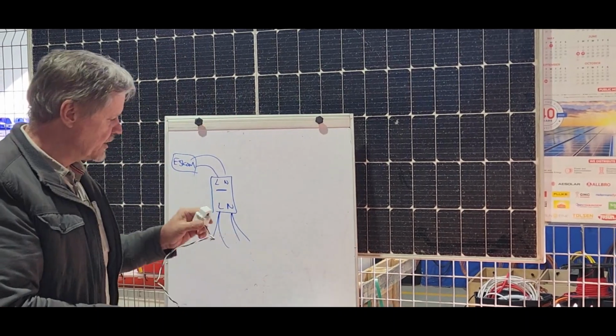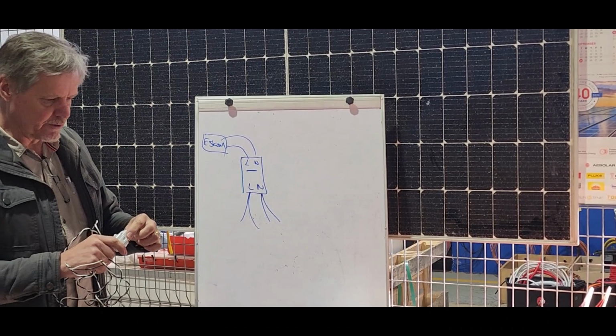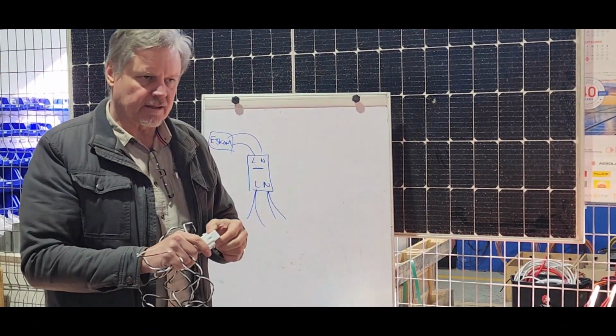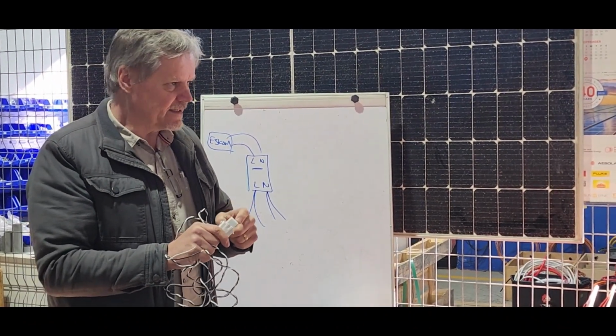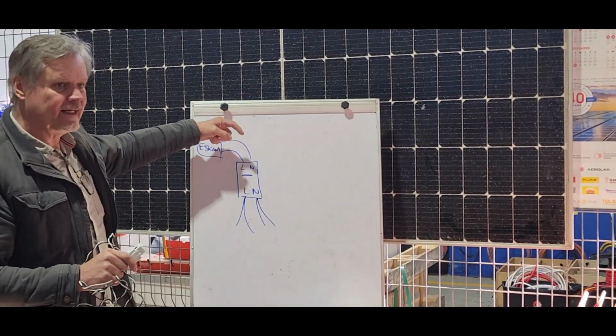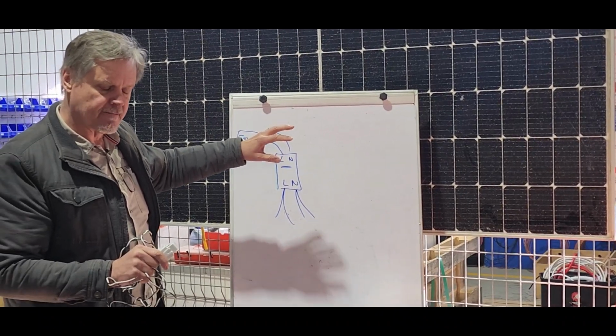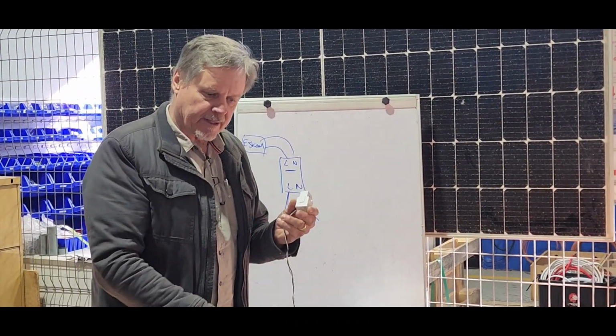So let's talk about which cable you connect this on. With the Sunsynk and all the installations we do, depending on the application, but 9 out of 10 times, we want this CT to tell us, if this is your main breaker in your DB, what is coming from Eskom. We want to measure the Eskom inputs. All right. Now let's quickly talk about the black and the red.